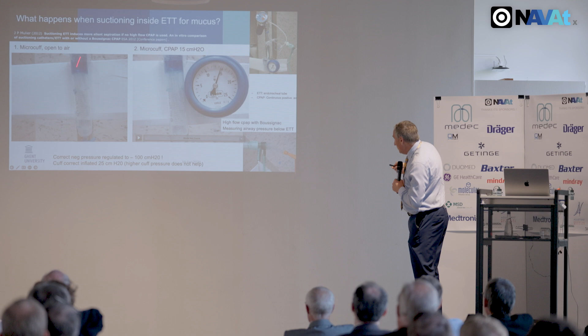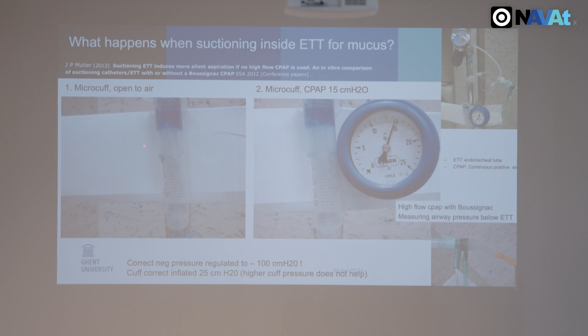There's another aspect also: if you do suction, and you shouldn't do that at the end of the procedure, but in intensive care, due to a lot of mucus, we have to suction this mucus away. If you go in with a suction catheter, and normally you should be starting, showing, but no, he didn't start anyway, but look, the moment you go in with a catheter, you get real negative pressures inside, and all cuffs, also the microcuff, will start leaking immediately. And this has to do with the real negative pressures here.